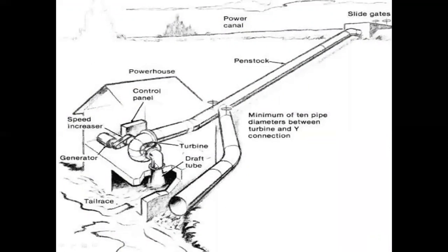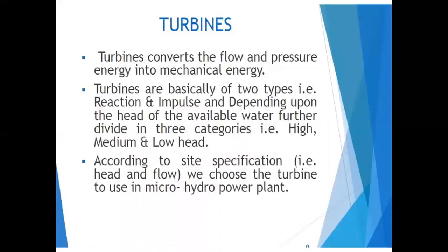The turbine converts the flow and pressure energy into mechanical energy. Turbines are of two types: reaction and impulse turbines, and depending on the available head of water, they are further divided into high, medium, and low head categories — Pelton, Francis, and Kaplan turbines. Normally we use a Pelton turbine because the head is typically high.